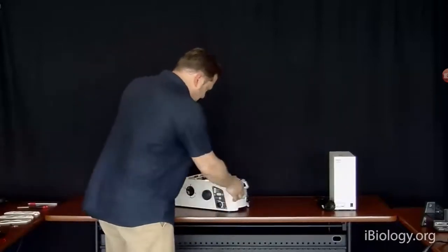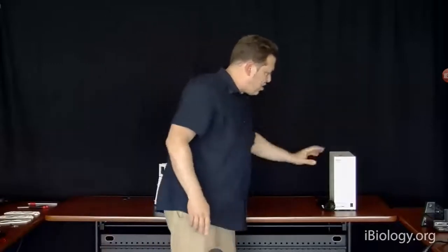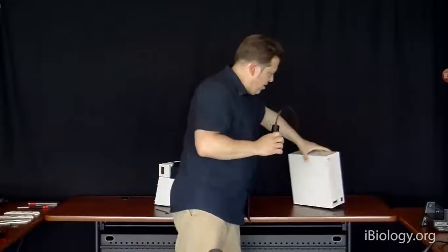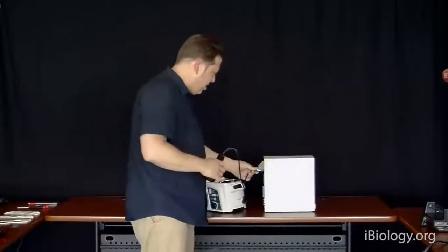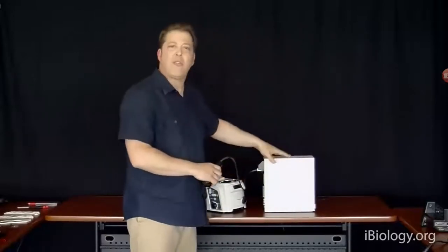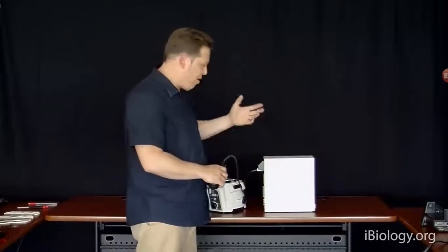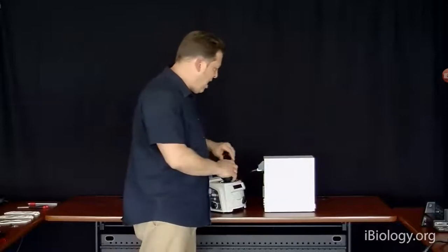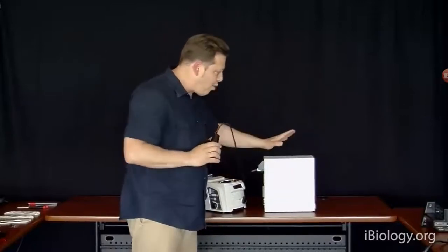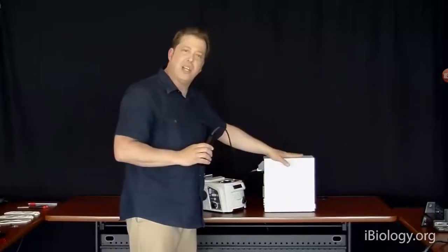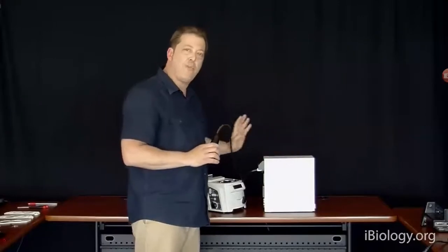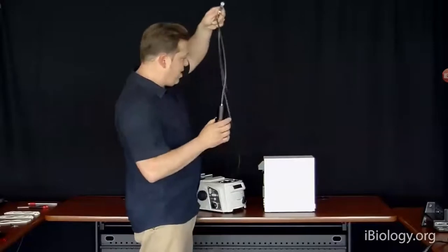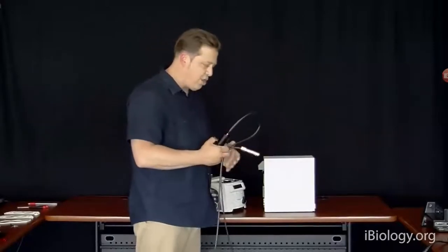So the last thing to go through here now is just the fluorescence light source. And basically, this is much more common now than high intensity lamps. There are similar light sources to the lamp house that we showed for the transmitted light, but most fluorescence systems now are using light sources that are remote from the microscope, which gets the heat away from the microscope. This one is a metal halide system. We'll show you the bulb.